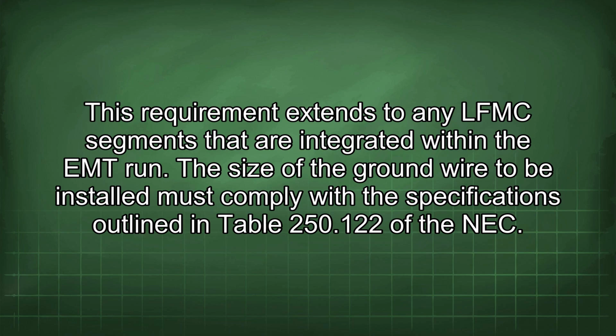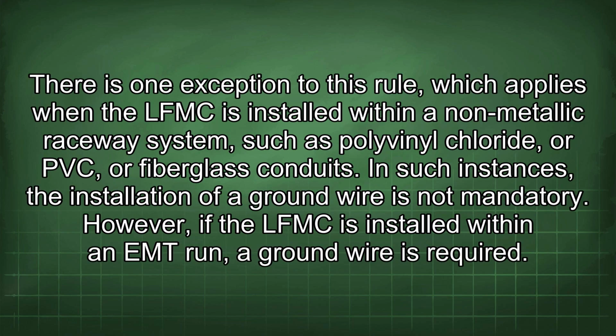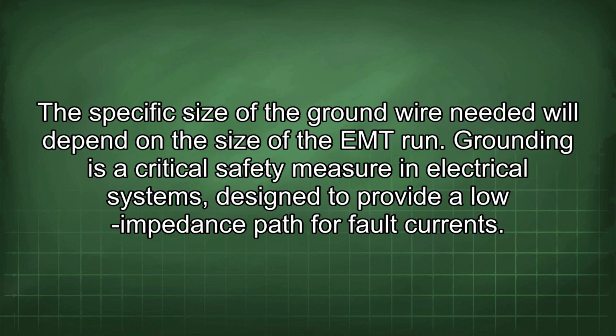250.122 of the NEC. There is one exception to this rule, which applies when the LFMC is installed within a non-metallic raceway system, such as polyvinyl chloride or PVC or fiberglass conduits. In such instances, the installation of a ground wire is not mandatory. However, if the LFMC is installed within an EMT run, a ground wire is required. The specific size of the ground wire needed will depend on the size of the EMT run.